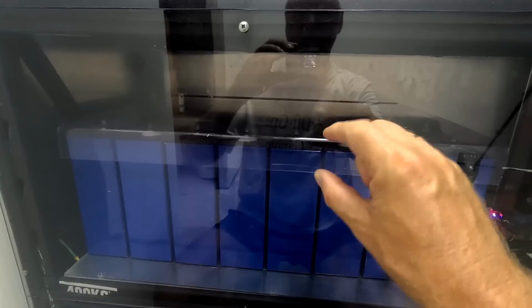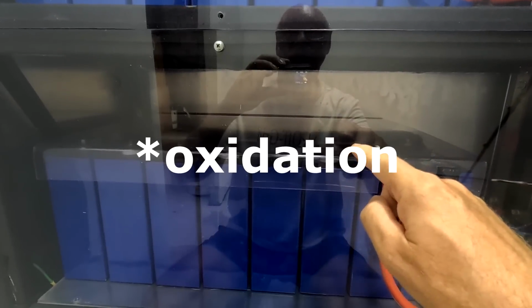Even though they have a lower resistance themselves than the copper bus bars due to the sheer size of the aluminium plates, I think there's a bit of oxidation between these aluminium bus bars and the aluminium terminals of the batteries. Over time this has caused this battery to charge a bit slower until it's fully charged and we raise the voltage to about 55 volts.